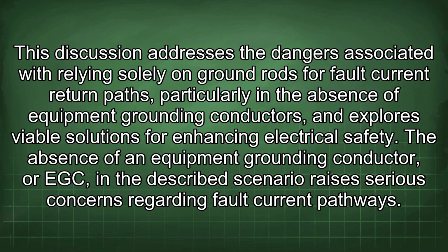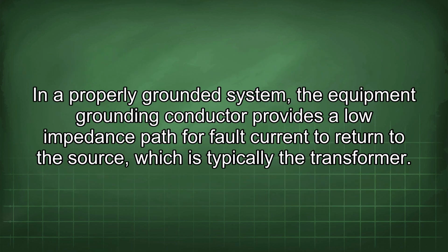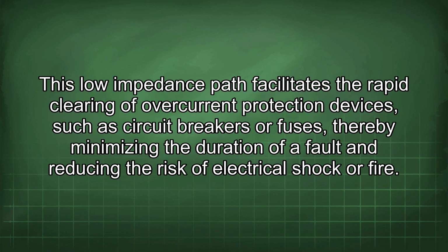The absence of an equipment grounding conductor, or EGC, in the described scenario raises serious concerns regarding fault current pathways. In a properly grounded system, the equipment grounding conductor provides a low impedance path for fault current to return to the source, which is typically the transformer. This low impedance path facilitates the rapid clearing of overcurrent protection devices, such as circuit breakers or fuses, thereby minimizing the duration of a fault and reducing the risk of electrical shock or fire.